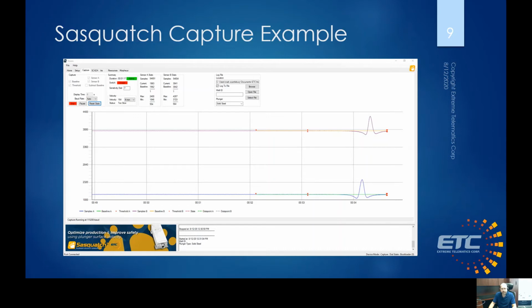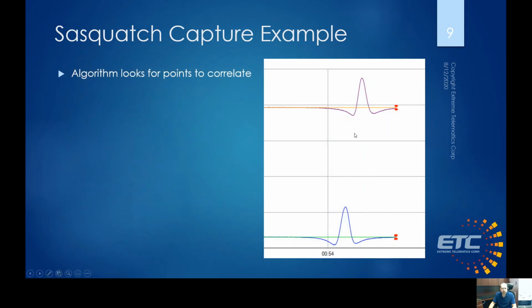So if we zoom in, it's looking for points that it can correlate. You can see there's definitely a time shift here, but the waveforms look pretty much identical. This plunger traveled by at a relatively consistent speed, so the waveforms look the same size. But because it might travel by and accelerate or decelerate, we look for things that are common or constant, which is the minimum, the maximum, when we cross the baseline.